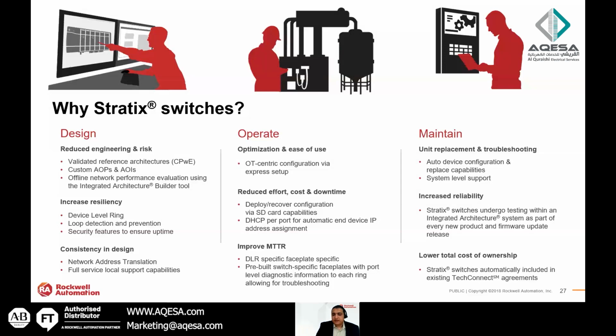Improve mean time to repair by having DLR specific faceplates with pre-built switch specification. You can add instructions inside the logic CPU so the CPU monitors the state of the switch. If the switch is down, the faceplate on the SCADA or HMI can tell you the switch has some problem, please fix it. You can have auto device configuration, and with our asset management software, the configuration of the Stratix switches can now be stored on the asset management disaster recovery server.